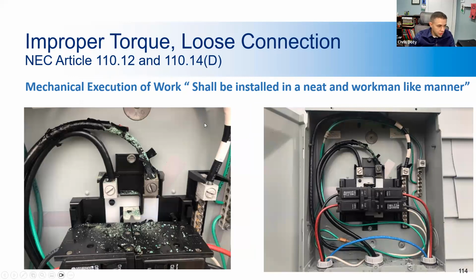Here we have what is probably the most interesting error in this presentation. These two pictures are of the same panel. Here you can see it's an outdoor panel. The left lug looks pretty good. The right lug is discolored, and the insulation for the conductors is in very bad shape. So what happened here is the right lug was not tightened down correctly, and the wire was loose in the lug. So it didn't have a really good connection, and the temperature of the wire would go back and forth, hot and cold, hot and cold. Then it eventually burned off the insulation. And then since it's outside, condensate got in there and caused the copper to corrode and flake off.